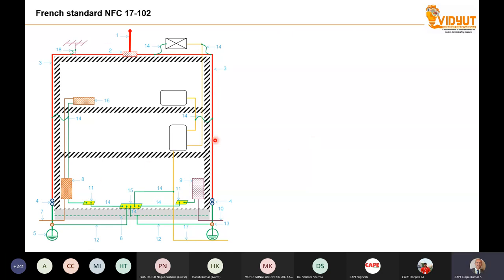Now, this is the picture of how to install an ESE rod, explained in the early streamer emission standard, which is the French standard. Remember, worldwide, there is only one standard which accepted early streamer emission, which is the French standard. From the French standard, other countries also adopted it, like Spain, Portugal, and all the nearby countries. Now, this picture is the explanation of how to install a lightning ESE rod in a building. It consists of one or more air terminals. This air terminal is the ESE rod, connecting components, down conductors.